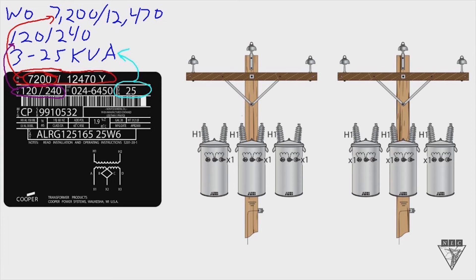So when we're banking transformers together, there's two other things that we need to look at. And the first one I'm going to circle is the impedance. So when you think of impedance, think of resistance. And you want to try and get three transformers that have the impedance as close to each other as possible. So we've got 1.9% as our impedance.